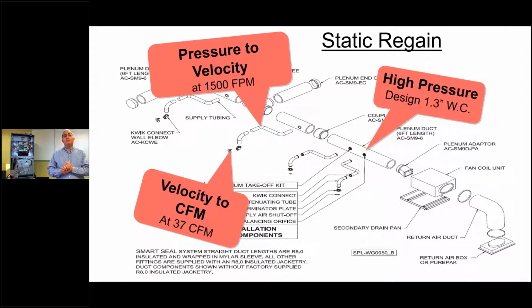So on occasion, we will see a room that's far away from the plenum. Could take 40 to 50 feet of 2-inch drops to get there. You did your calculations, and your calculation said you only needed 2 drops. But in reality, you're losing 5% for every additional, I believe it is 10 feet. So now those two outlets may have to be bumped up to 4, possibly 5, because of the length of the 2-inch runs to get there. That could be a problem because that room is so far away, you may have all your outlets in the room in one location. Kind of looks a little strange, and I don't want to create a lot of noise if I have all my outlets in one location.